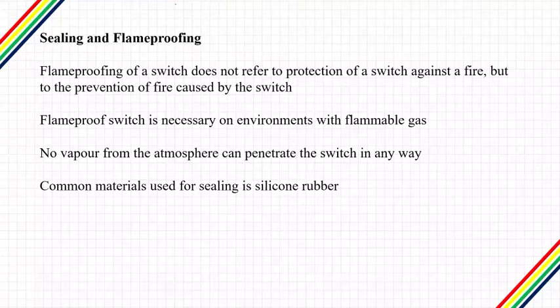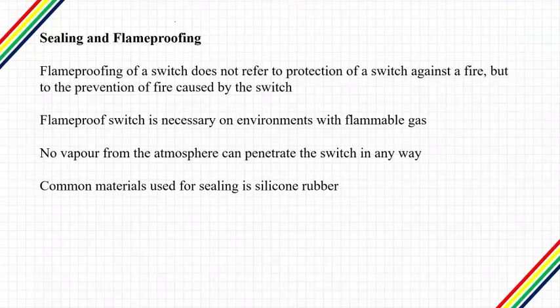Flameproofing of a switch does not refer to protection of the switch against fire, but to the prevention of fire caused by the switch. This is used for the protection against flammable gases in the surroundings, which can cause fire whenever there is arcing or sparking on the switch contacts. These hazardous environments include mines, chemical stores, and processing plants that make use of flammable solvents, where sparking and arcing should be minimized or eliminated.